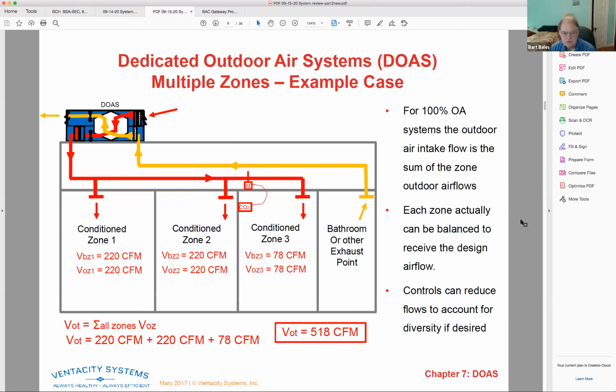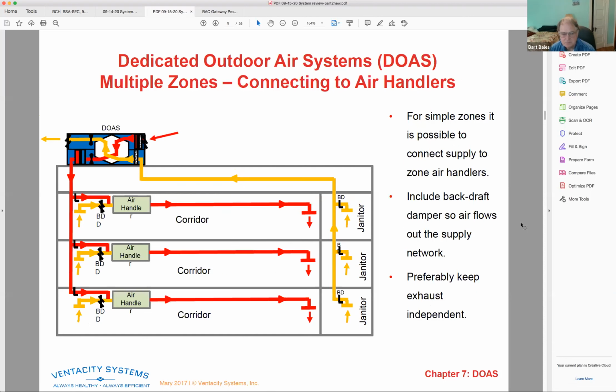And this is just showing that if you have a dedicated outside air system, you are delivering the air without connecting it to an air handler, and you're not using it for heating and cooling. You're using it just to deliver the ventilation air. And what we're finding is decoupling ventilation air from heating and cooling gives us a bunch of advantages. So next slide. This is just showing us a multi-zone dedicated outside air unit. Next slide.